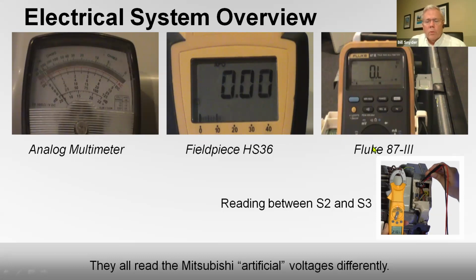If we go over here to the Fluke meter, it's a lot faster, responds a lot quicker. So up here, you will see some voltages, and then there's also an analog meter on the bottom here, which looks a little different than this. So you've got to get used to what your particular meter will do. As you can see up here, we are seeing voltages. It changes from 9 to 24 to 14 to 16. It just keeps bouncing around. And then the analog meter on the bottom is bouncing around. All three of these indications that we've just seen here are good indications that the system is working properly.